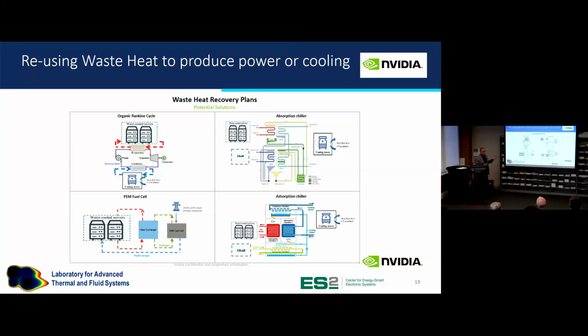The heat coming out of data center cooling systems is probably going to be about 60 to 70 degrees Celsius at most. The problem is that for a system like this one, which generates electricity, the conversion efficiency is only going to be about 6%. That's the problem with recovering waste heat.